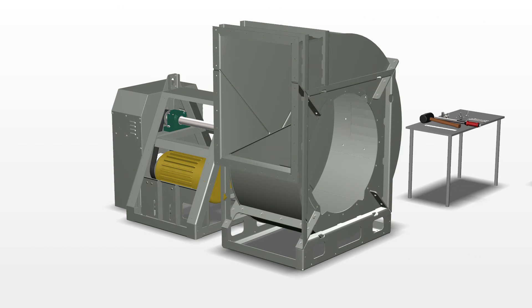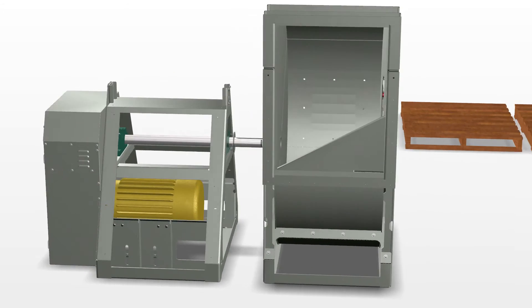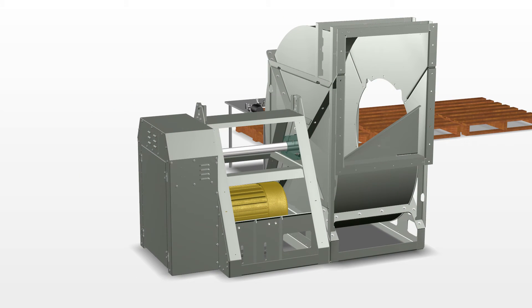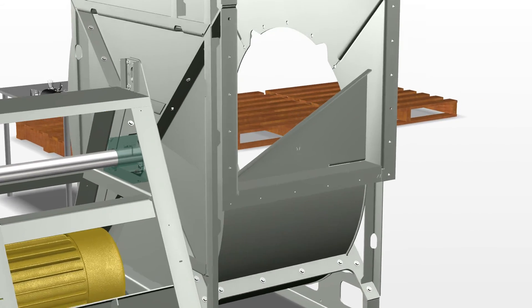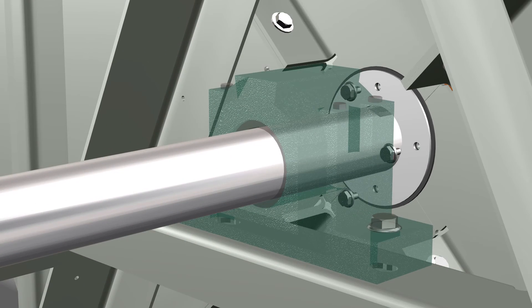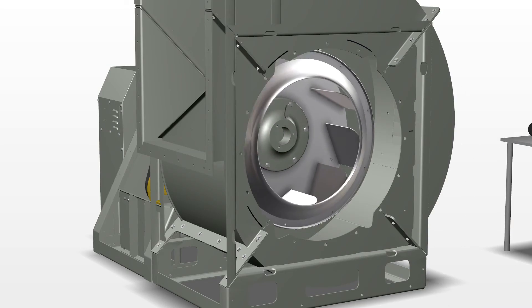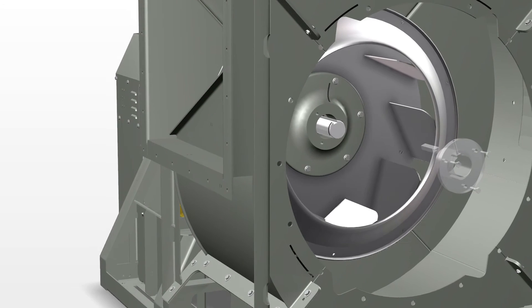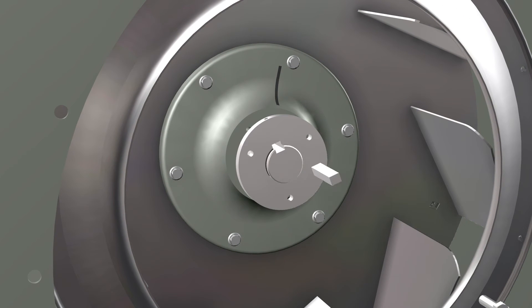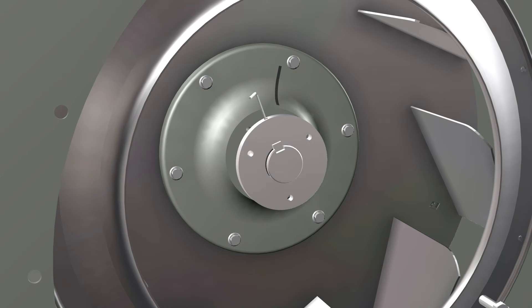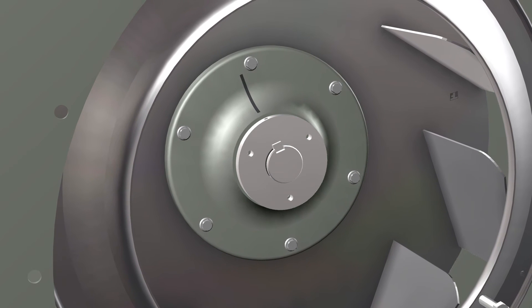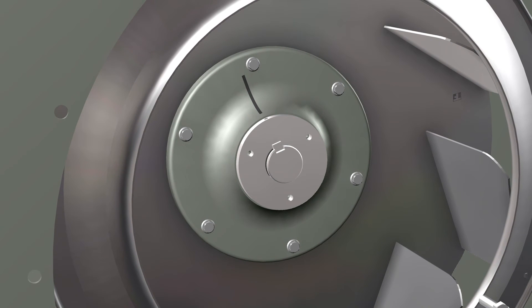Once the housing split bolts are tight, move the housing to the pedestal and bolt the two pieces together. If there's a seal, bolt it back into place. Place the wheel on the shaft and slide the bushing on the shaft to the scribe mark or the measurement you had noted before removing it. Tighten the set screws in the bushing. Pull the wheel hub onto the bushing. Make sure the key is lined up with the mark on the wheel hub. Snug the bushing bolts to the wheel hub.